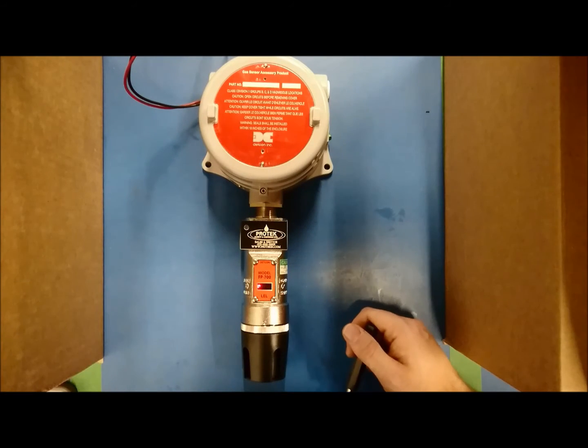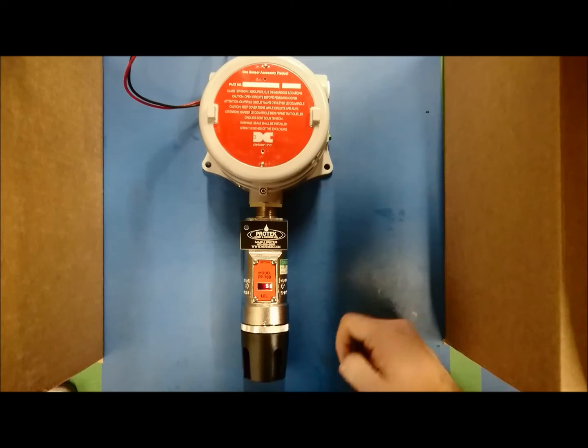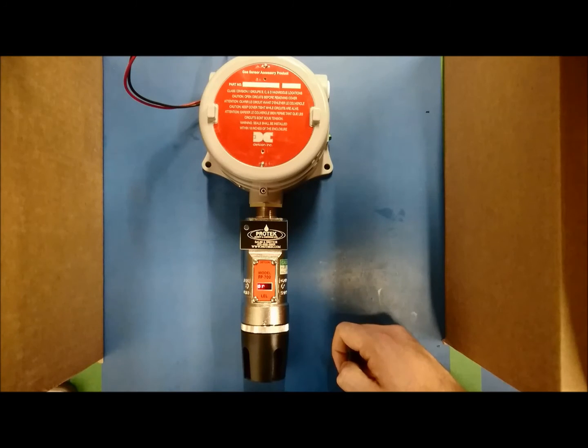If you do not need to change the cal factor, you can wait 10 seconds and the unit will go back to operational mode. If you wish to change the cal factor, hold the magnet over PGM2 until an arrow pointing right appears.